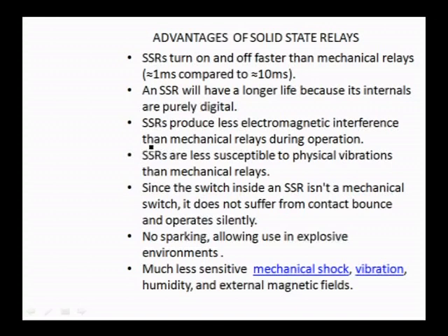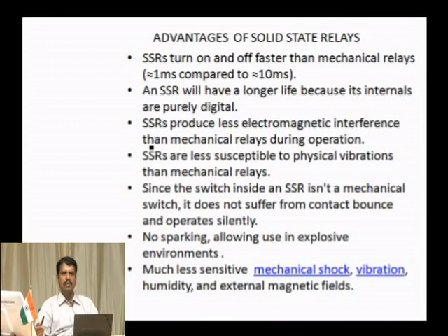Let us summarize the advantages. I already told you it is faster. Solid state relays are definitely faster than mechanical relays. There are no moving parts, so the time delays associated with them are not there, and they are very fast. They also have a long life, because the internals are purely digital, with no moving parts and no arcing. So the life will be longer.